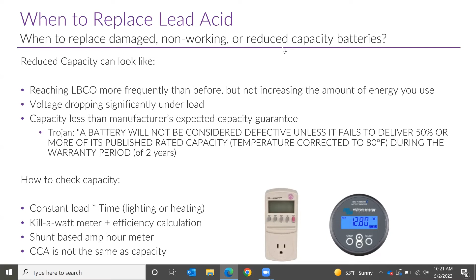Another reason you may want to replace an existing lead acid battery bank: maybe your loads have increased. One issue with lead acid batteries is you cannot expand on an existing bank. So if you've got a 5 battery bank installed in a customer's house and they add an electric washer dryer, and it turns out they need 3 more batteries, well, if those lead acid batteries are more than a few months old, there's no good way to add additional batteries to that bank. You'll simply need to sell or recycle those batteries and get a brand new bank of the correct size. This is why there's such an advantage to LFP batteries—you can actually add to them over time, anytime in their life.